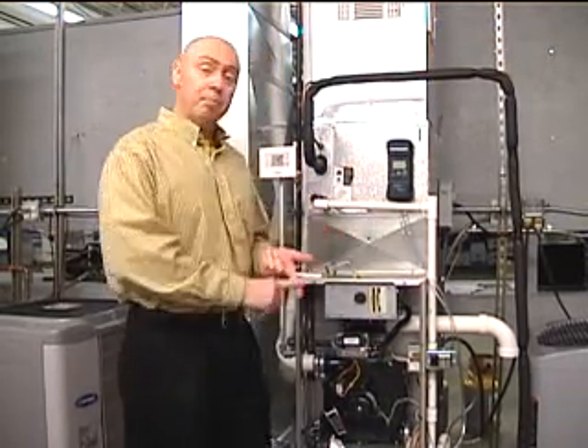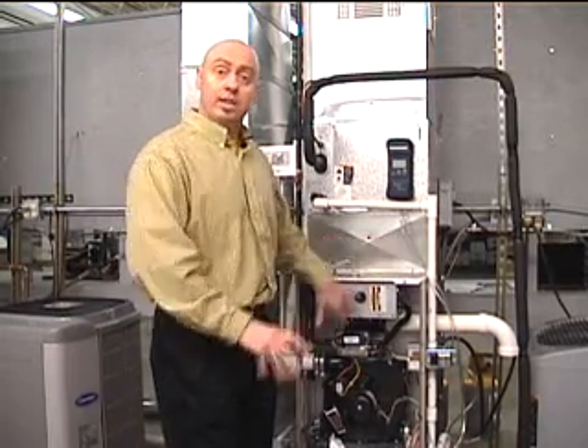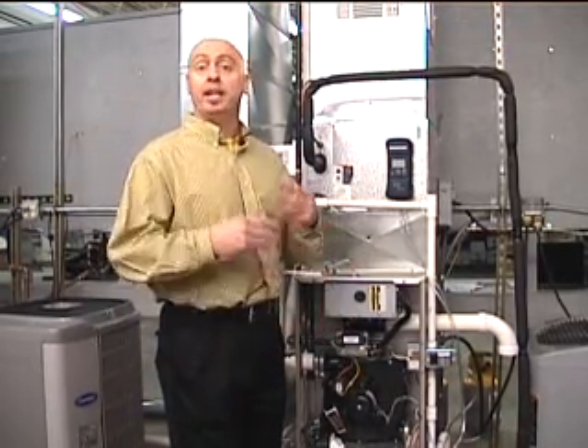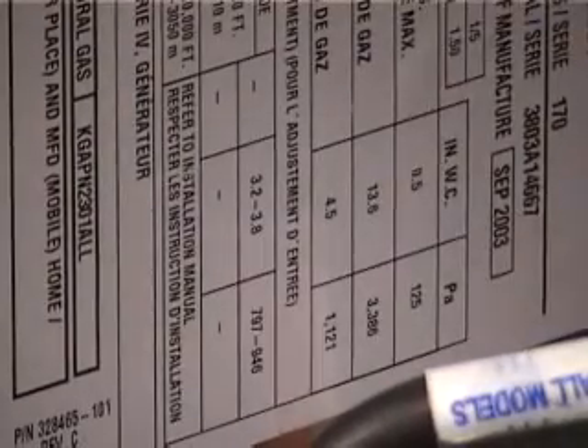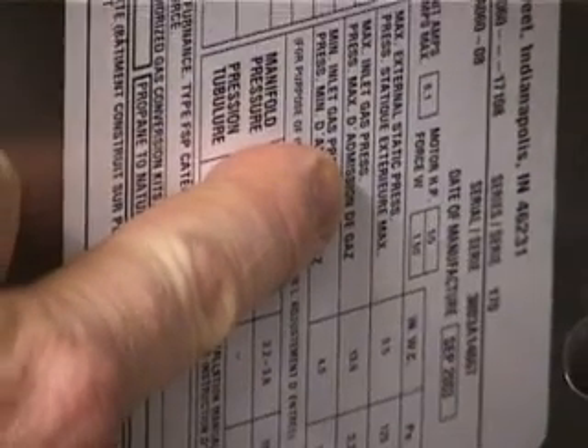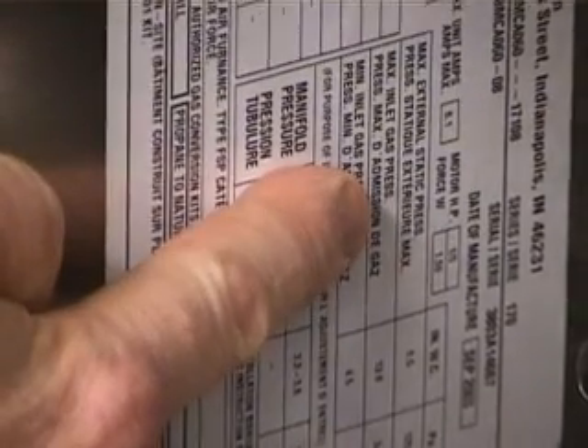The guys always go and look at the name tags. It'll give you the model number, the serial number, temperature rise, gas pressure. But one thing that is also listed on that nameplate is the maximum certified external static pressure. On the nameplate of the unit, you will find important information like the model number, serial number, voltage, gas pressure, temperature rise, things like that. But one of the things that is listed on this piece of equipment, you can see right here, maximum external static pressure. That is the maximum allowable external static pressure for the unit. That is what it's certified against. If you stay underneath that, you'll get all the airflow delivery that the equipment is rated for. If you go over that, the airflow becomes compromised. So you always want to stay under the maximum level.